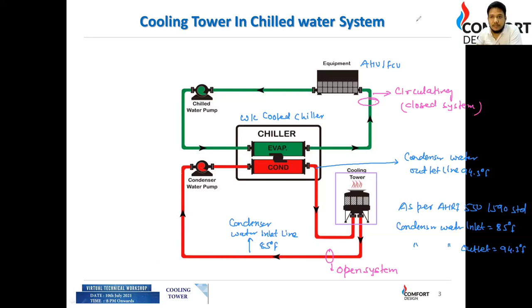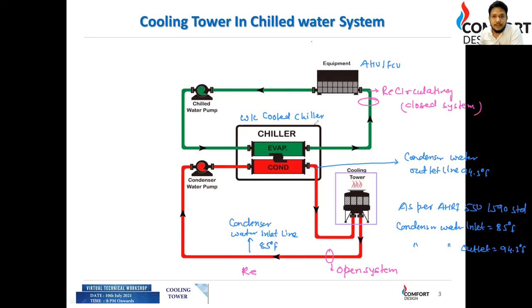Both sides are recirculating systems. In the chilled water loop, water from the chiller comes via the chilled water pump, goes to the evaporator or the cooling coil, and returns back — it recirculates. Similarly on the condenser water side, the water also recirculates, but that part is an open system.